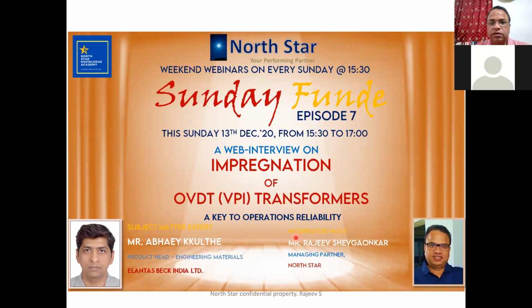So what is important is the moisture level and then the temperature. There are detailed studies and graphs available, which I will share some other time, where it is clearly established that the better the vacuum, the lesser the temperature required to filter the oil. So whenever you are seeking filtration services, please ask your guy that your vacuum should be good, and please see the vacuum gauge. Normally their vacuum gauges are not of sufficient range, or their vacuum systems are not that good. Normally filtration guys focus on the heating elements and heating system. They rarely give attention to the vacuum.